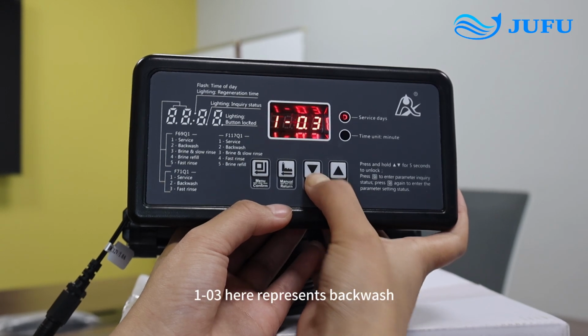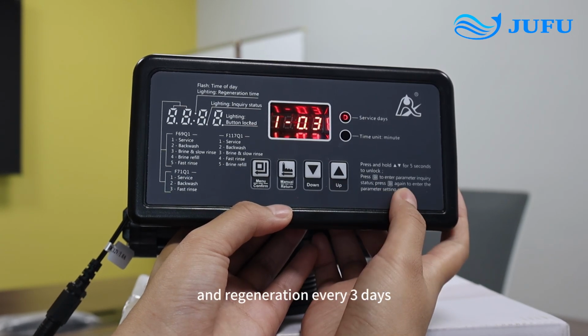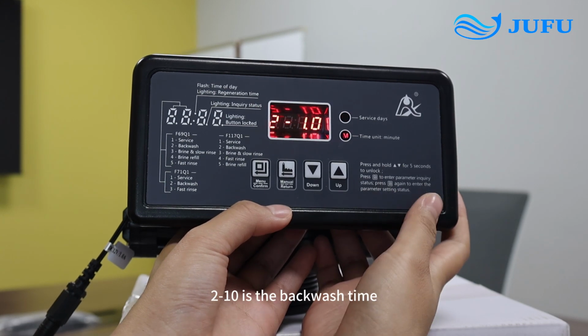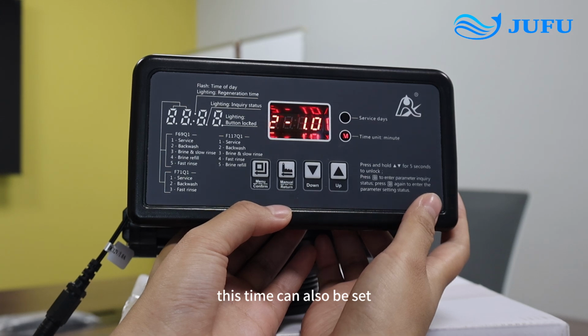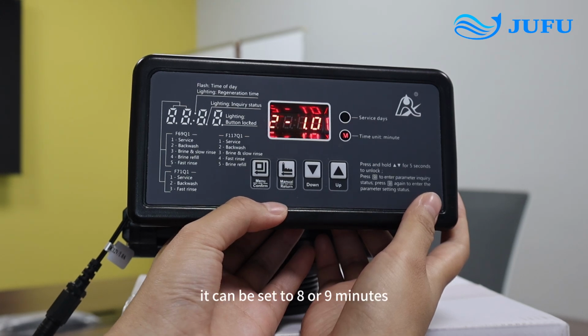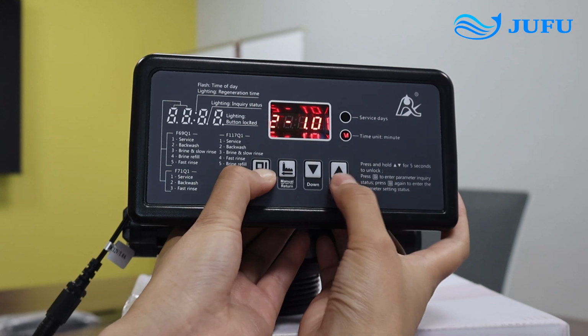So here we can set it to 2:50 a.m. Similarly, 103 here represents backwash and regeneration every 3 days. 210 is the backwash time. This time can also be set. It can be set to 8 or 9 minutes.